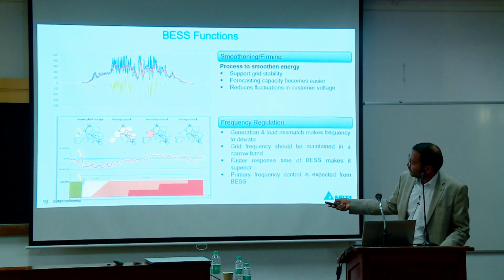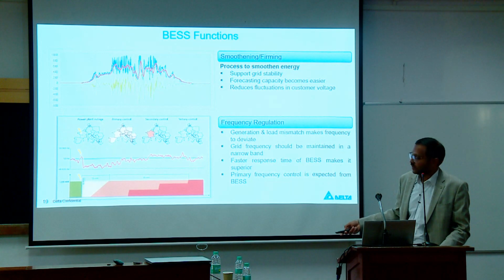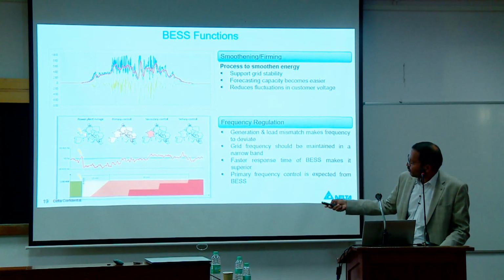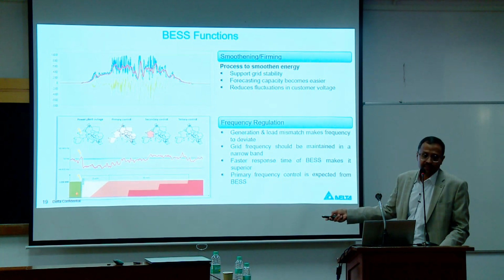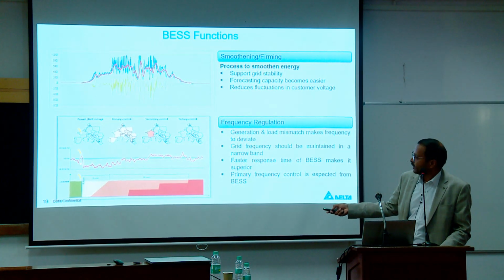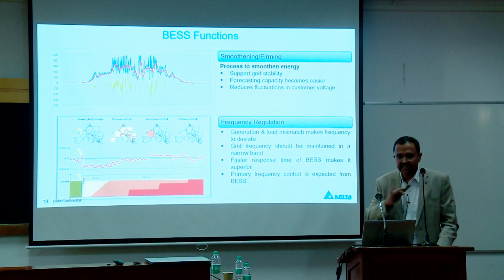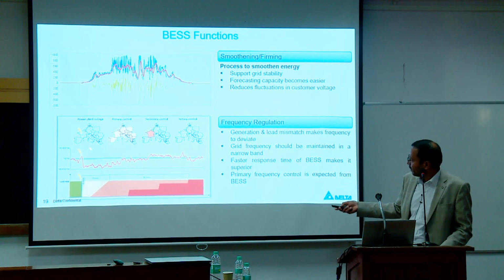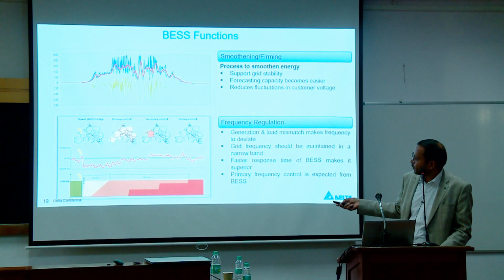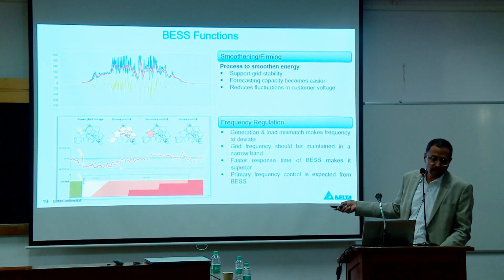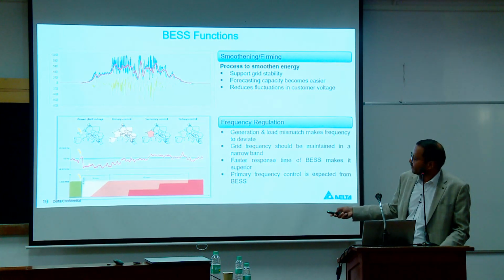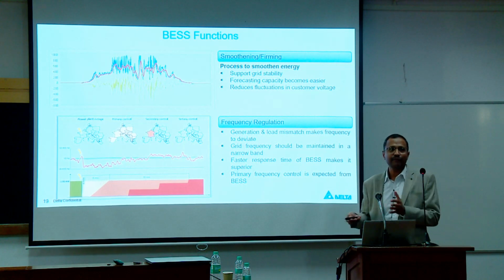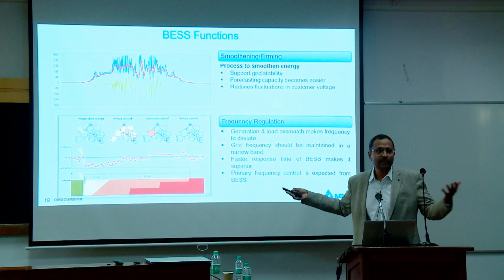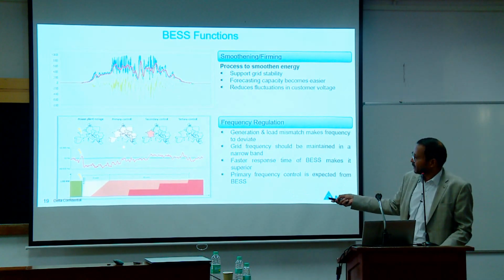So what is this primary frequency control? Let's take Europe, say in France, one power plant goes on outage. The frequency, which was stable, falls down the moment the shutdown happens. The one that kicks in first, within 0.5 minutes, is whatever is connected to power electronics, because nothing else can turn on in such a short time. Power electronics distributed all over Europe kick up, for example battery energy storage distributed all over Europe kicks in. So the frequency either stays or tries to improve, but batteries don't have enough energy, because a battery cannot give you hours of energy, as the investment becomes very high. Typically what's expected is 15 minutes of support.